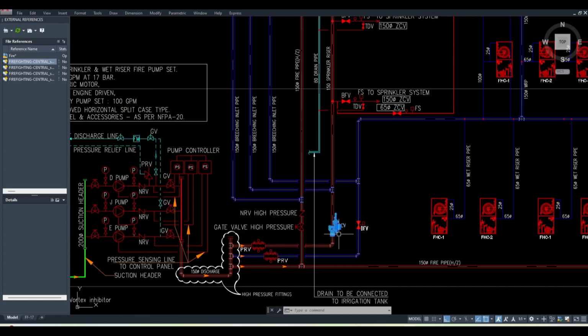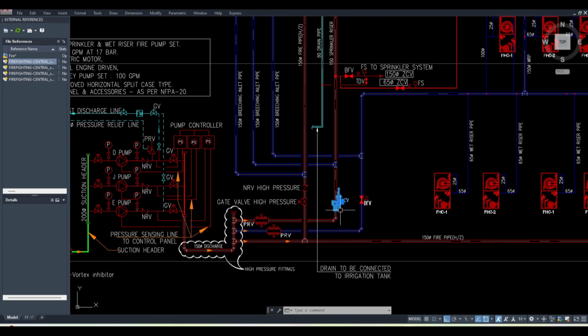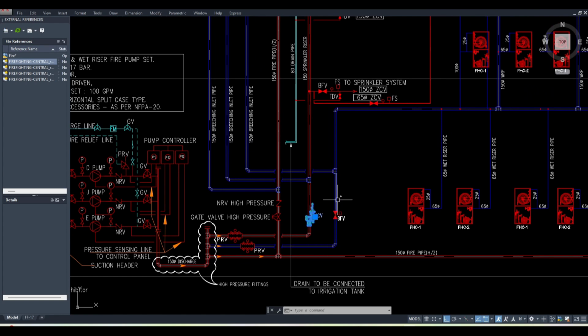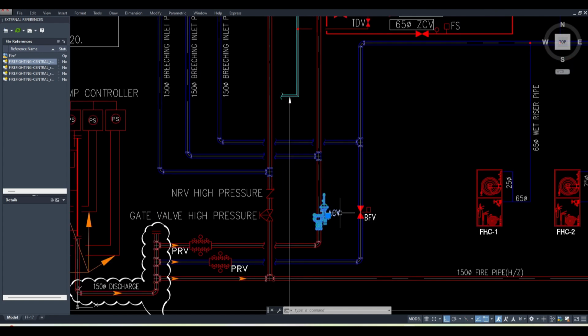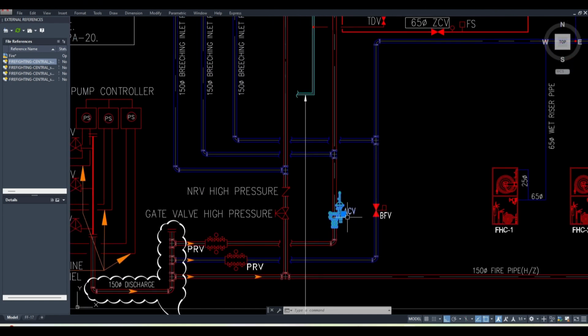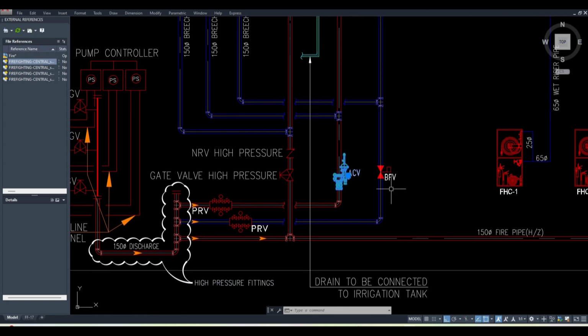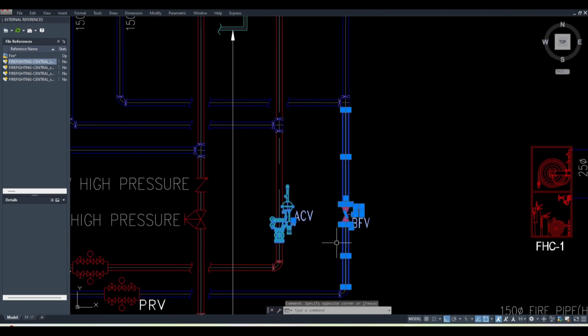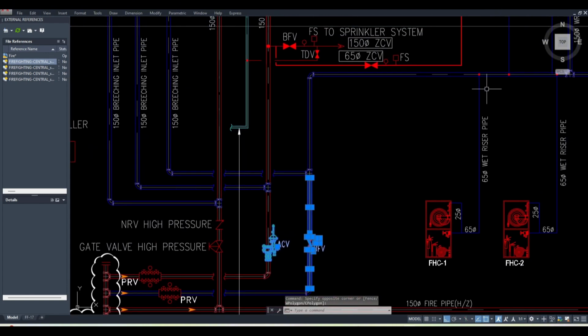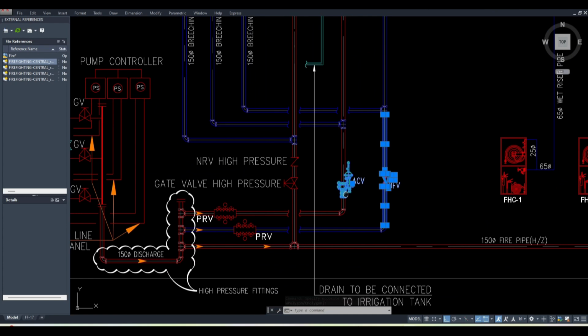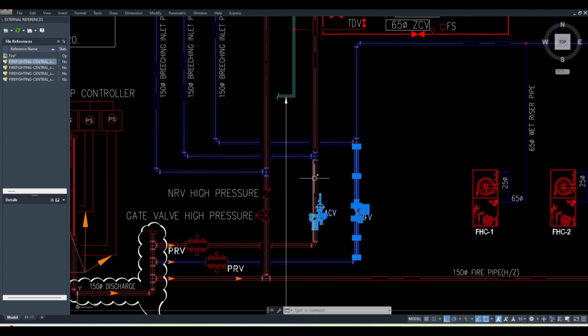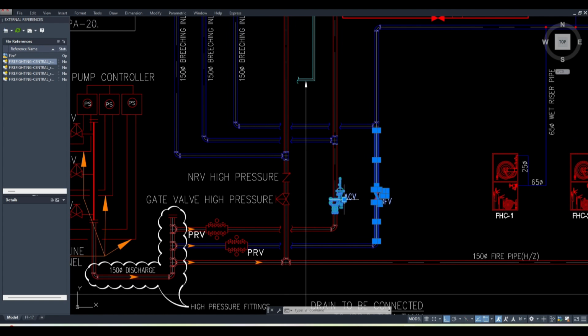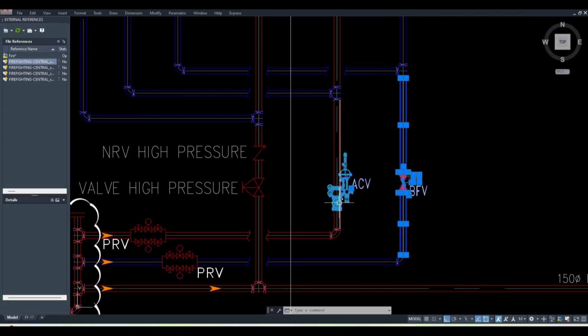This connection has to happen after the alarm check valve. And if you are taking a wet riser system connection from the same line, the wet riser connection has to happen before the alarm check valve. These two things are critical, you need to understand this. So whenever you take the branch for the wet riser system, it must be connected before the alarm check valve. You cannot connect it after the alarm check valve. Now, what is the use of the alarm check valve? First of all, it is a check valve, so it allows water to go from one side to another side.